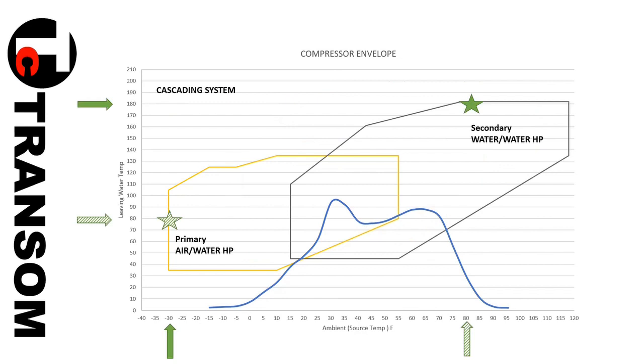I had a question just to make sure I'm following. The compressors are not new technologies, but the controls to make the step, that's new, right? Yes, it's a very good question. If you took each part and chopped it up, it's very traditional technology that's been proven out before. It's the repackaging of it for this application that makes it work, and that's the new part. Like the embedded coils, taking what's normally refrigeration type compressors, like for walk-in freezers and refrigerators, and applying it to heat pumps. Each one in itself is not that much. The compressors are very standard proven technology. So again, as long as you stay inside that envelope, then you're okay.